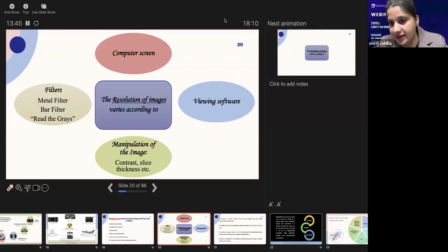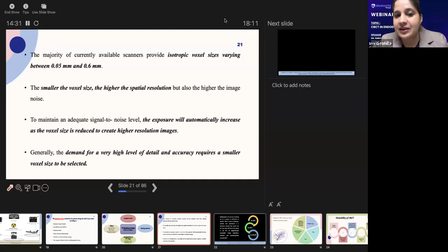So the majority of the currently available scanners provide an isotropic voxel size that varies between 0.05 to 0.6 mm. The smaller the voxel size, the higher the spatial resolution, but it also leads to higher image noise. To maintain an adequate signal to noise level, the exposure will automatically increase as the voxel size is reduced to create higher resolution images. That means if the voxel size is decreased, you have better resolution of the image, but you have to maintain a balance between the two so that the image noise is decreased. So generally, a demand for a very high level of detail and accuracy requires a smaller voxel size to be selected.